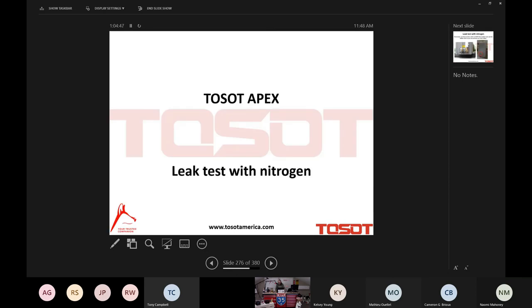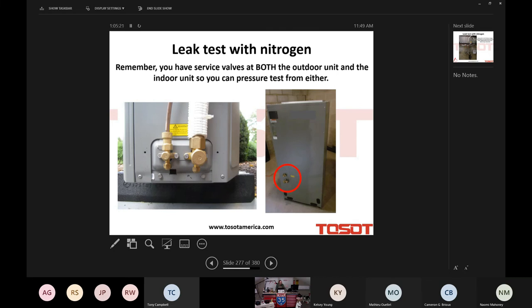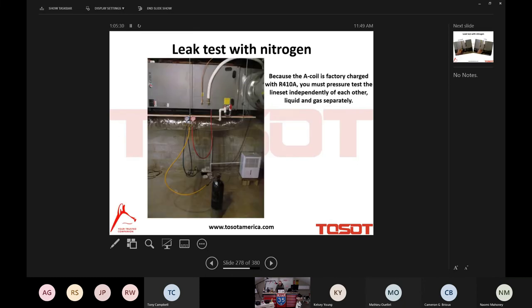Leak test. We're going to leak test with nitrogen, but remember where we started today. I told you that the indoor coil as well as the outdoor coil charged not with nitrogen, but with R410A. So all we are leak testing, think about this, my friends, all we are leak testing is the line set. We don't have an open end on either side. Both sides of that line set is closed because the coil on either side is charged. So all we are pressure testing is the line set. Again, the beauty of the Apex indoor unit is that we can start this process either at the indoor or the outdoor unit in the relative comfort of the basement of the structure, which is beautiful.